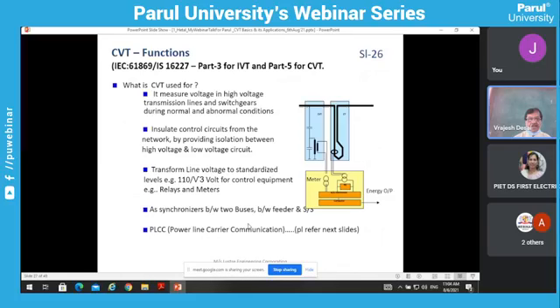It is also used as a synchronizer between two generating stations. Suppose we want to connect both generating stations through a bus, then this PT can be used, because you have to balance the voltage of generating station 1 with that of generating station 2. So this is used for that. The very important additional use is power line carrier communication. We will see it in the next two slides.